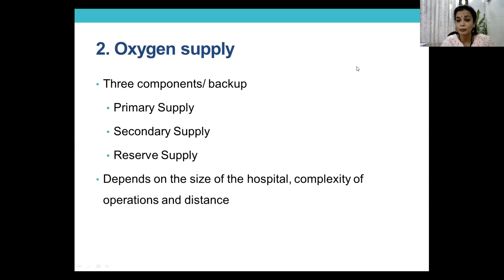Now, there are three main things I mentioned for your primary supply: cylinder related manifold, liquid medical oxygen, and the oxygen concentrator. If you're a small establishment and you have a manifold, it's not only one manifold. You have to have a backup and another backup. So the primary source here is your manifold with an auto changeover system. You cannot depend on your technologists and technicians to go and change over for you. It has to be an automatic manifold changeover system.